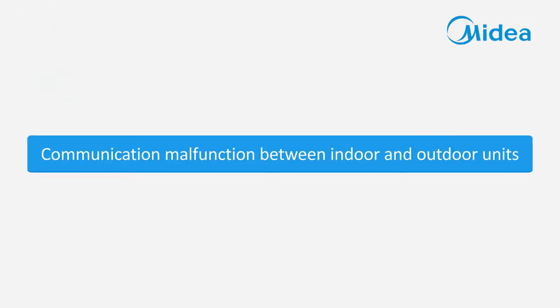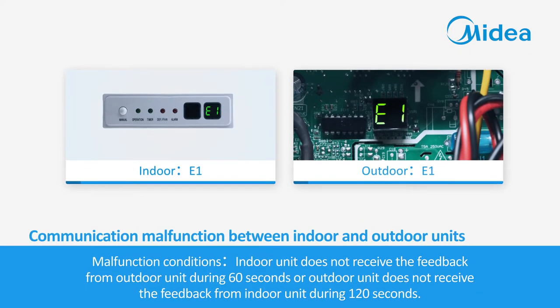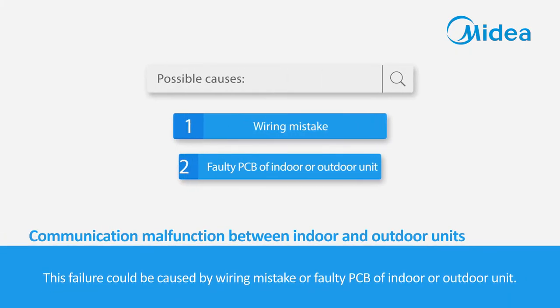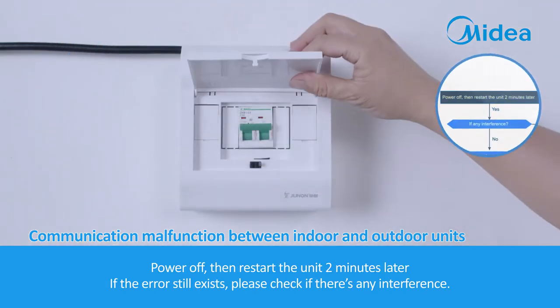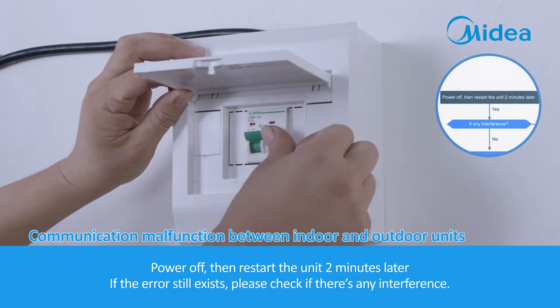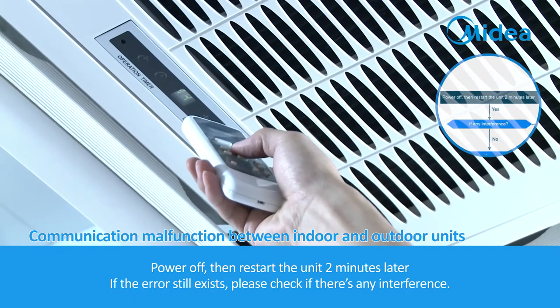Communication malfunction between indoor and outdoor units. Malfunction conditions: indoor unit does not receive feedback from the outdoor unit during 60 seconds, or outdoor unit does not receive feedback from the indoor unit during 120 seconds. This failure could be caused by wiring mistake, faulty PCB of indoor or outdoor unit. Troubleshooting: power off, then restart the unit two minutes later. If the error still exists, please check if there is any interference.